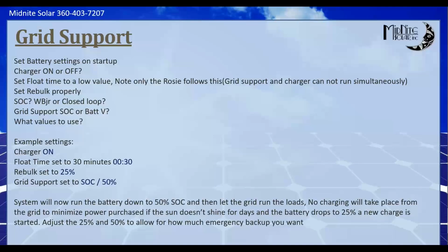Really what we're trying to do in this application is store every ounce of that solar power every day and use it throughout the night. The goal is never to roll back over to the grid at 50%, but if we do, the next day we want to still be able to harvest every bit of that PV that we can. And we talked about the reason to turn the charger off and on, and about setting float time.